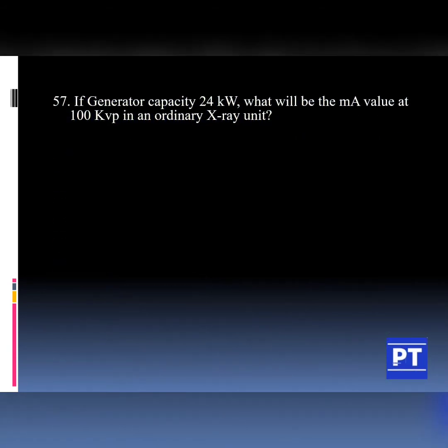Question number 57: If generator capacity is 24 kW, what will be the MA value at 100 kVp in an ordinary X-ray unit? MA means milliampere, which determines the current value, at 100 kVp. KVp means kilovolt peak, which is the voltage in an ordinary X-ray unit.